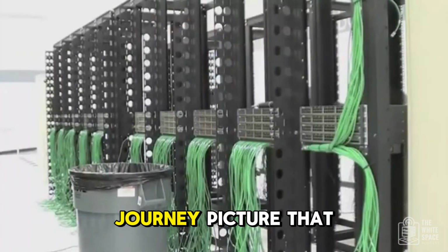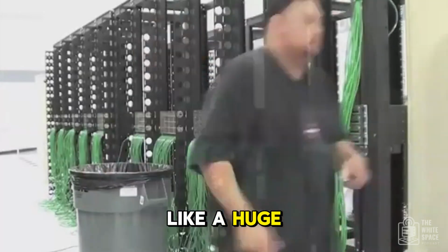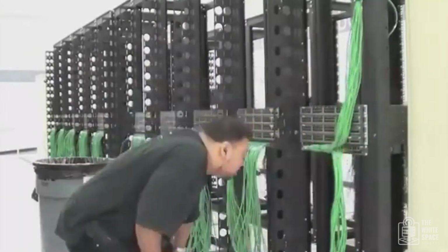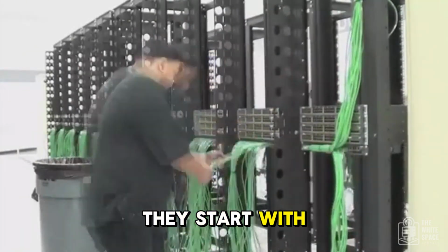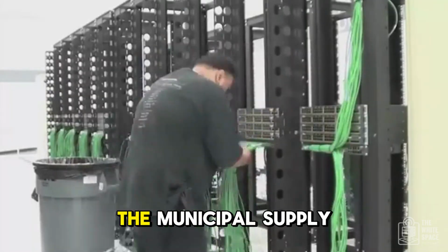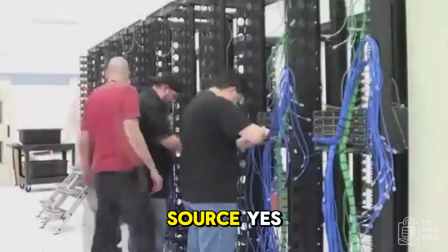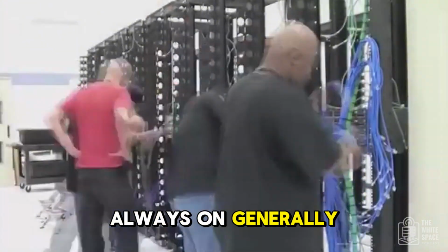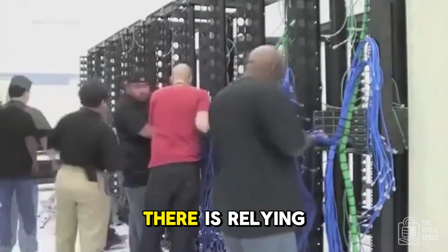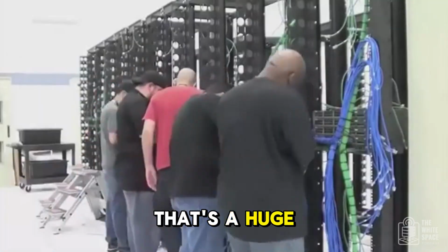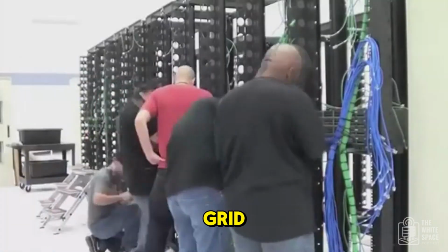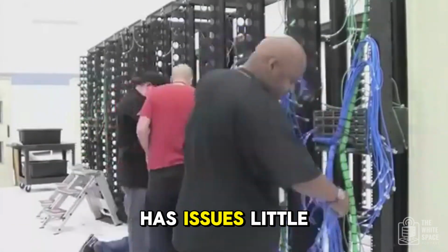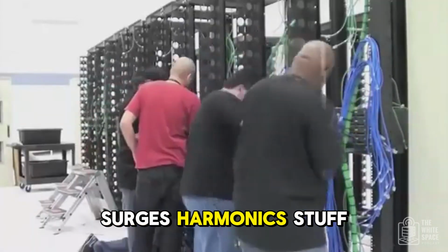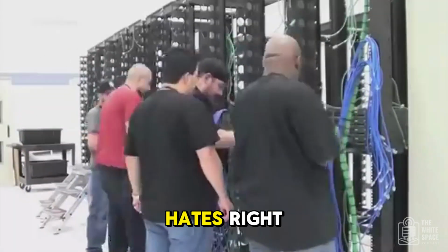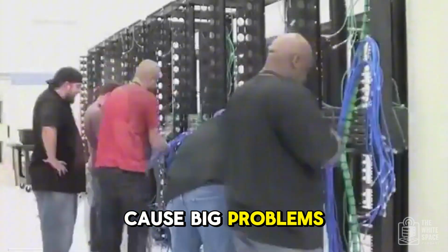Okay, let's start the journey. Picture that power grid like a huge river flowing towards the data center. Most enterprise places start with the familiar city power grid, the municipal supply—that's the primary source, always on, generally reliable. But relying only on the grid is a huge gamble for these critical sites. The grid has issues: little voltage dips, surges, harmonics, stuff that IT gear really hates. Tiny fluctuations can cause big problems.